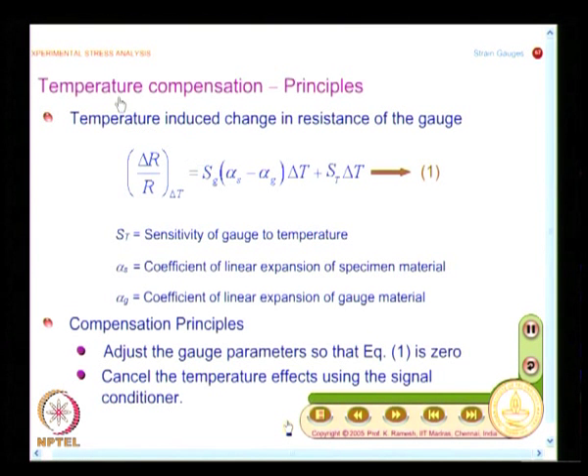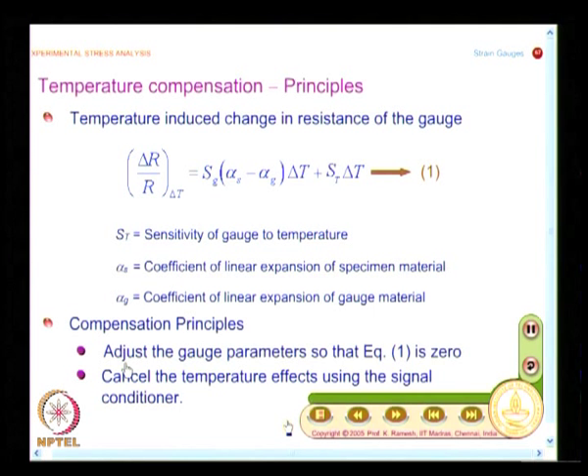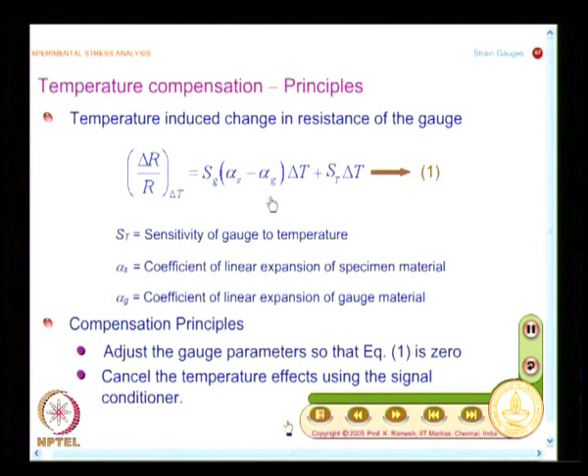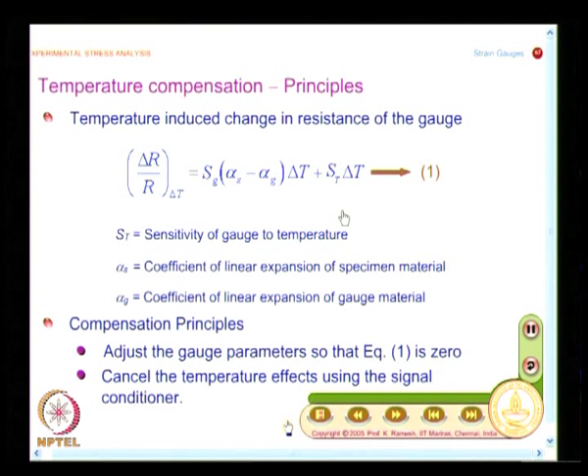When compensating for temperature effects, there are two broad approaches. One approach is to adjust the gauge parameters so that the equation equals zero. If I have a method to change alpha_G, I can handle this so that term 1 and term 2 compensate for each other, and I get what are known as self-temperature compensated gauges.